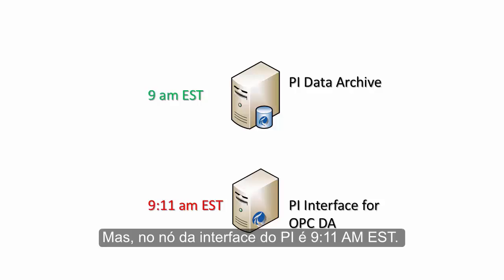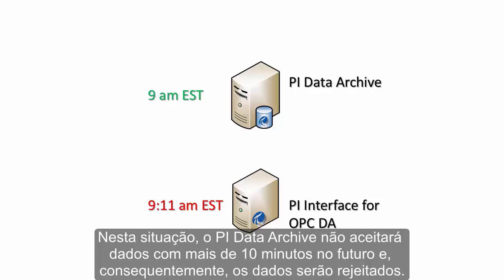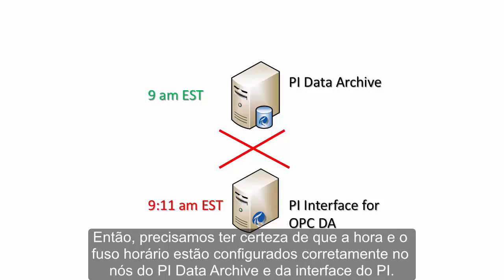Eastern Standard Time. In such a situation, PI Data Archive cannot accept data more than 10 minutes in the future, thus data will be rejected. So we need to make sure that the time and time zones are set properly on both PI Data Archive and PI Interface node.